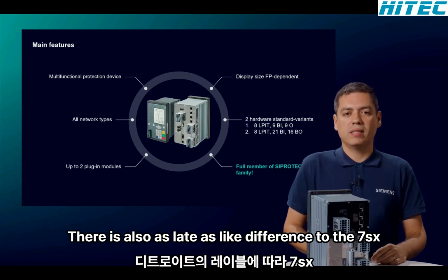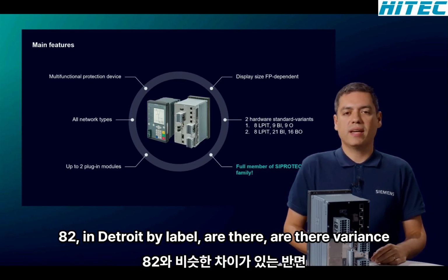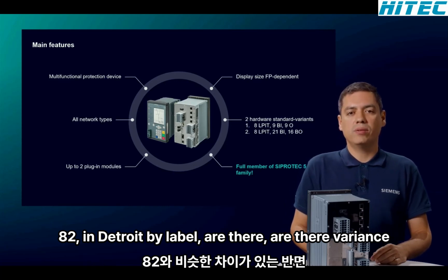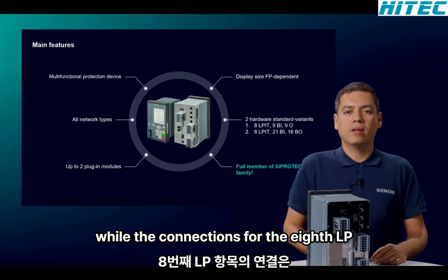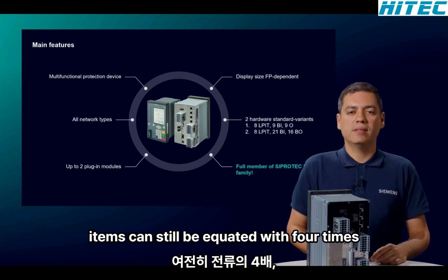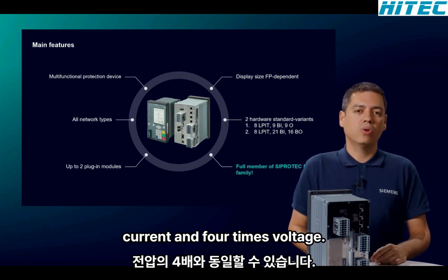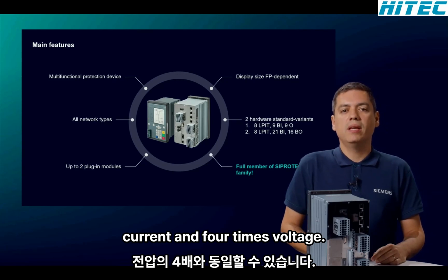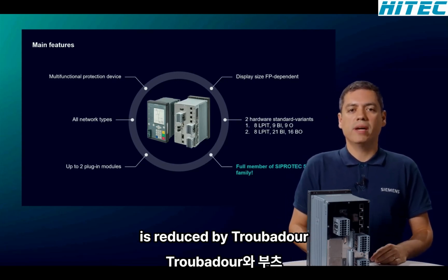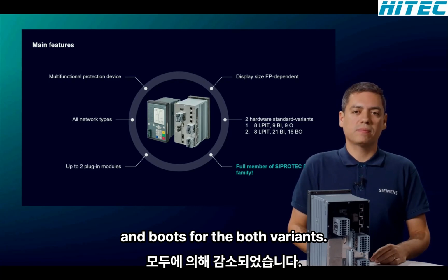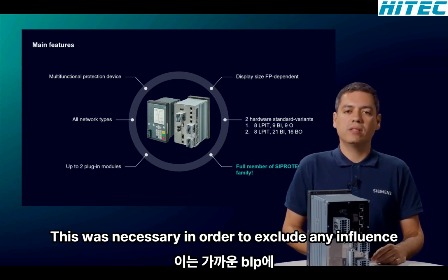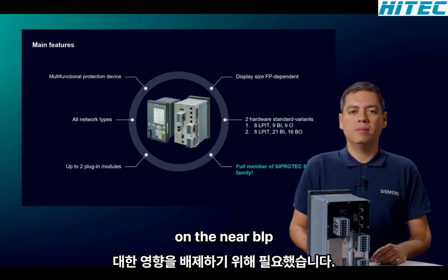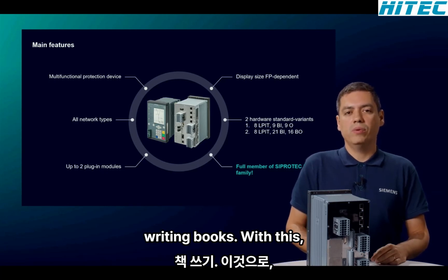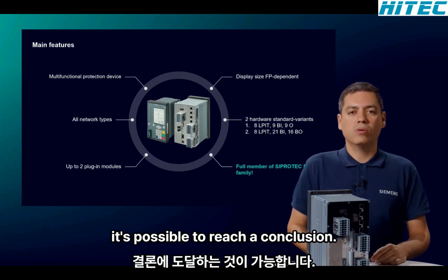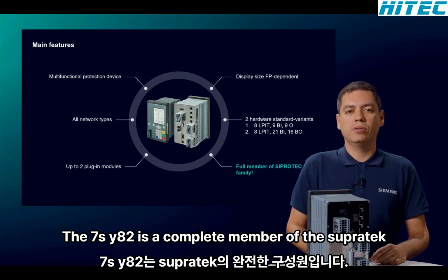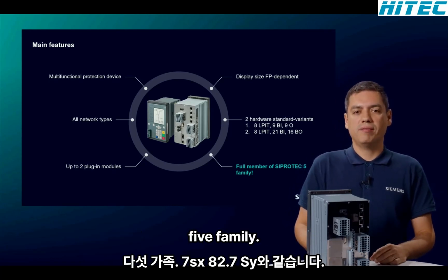There is also a slight difference to the 7SX82 in the 2 available hardware variants. While the connections for the 8 LPITs can still be equated with 4 times current and 4 times voltage, the number of binary inputs is reduced by 2 binary inputs for both variants. This was necessary in order to exclude any influence on the nearby LPIT inputs. With this, it is possible to reach a conclusion. The 7SY82 is a complete member of the SIPROTEC 5 family.